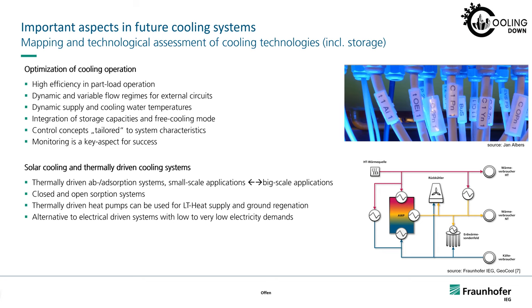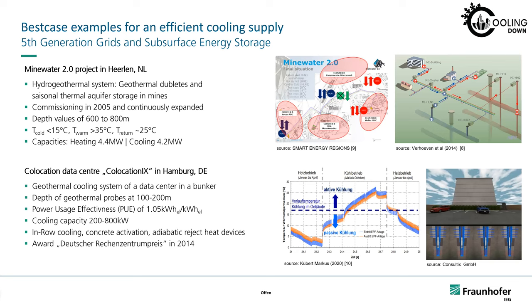Coming to some best case examples to strengthen this perspective: on the upper part we have the Minewater 2.0 project in Heerlen, Netherlands - a hydrogeothermal system with geothermal doublets and seasonal thermal aquifer storage in mines. Commissioning took place in 2005 and it has been continuously expanded, with depths going down to 800 meters below surface. For cooling, we talk about a temperature close to 15 degrees Celsius, and for heating about 35 degrees, so introduction of heat pumps is necessary. In terms of capacity, it's more or less 4 megawatts for heating or cooling.